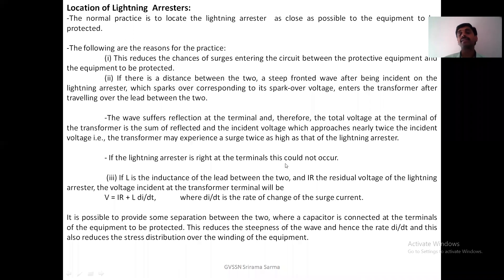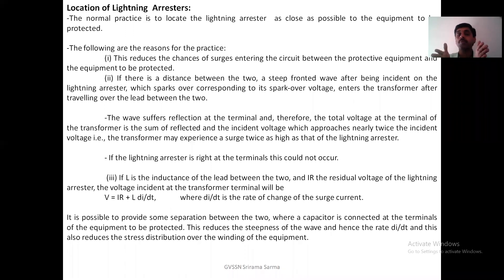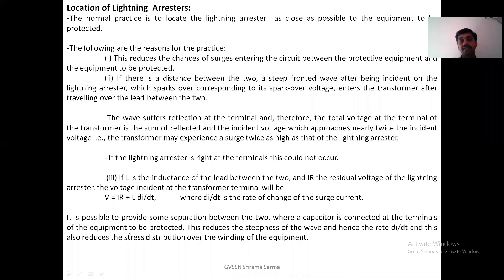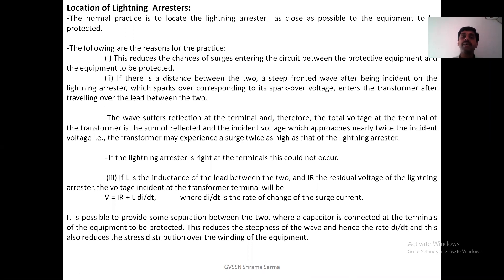Therefore, if the lightning arrester is right at the terminals, this could not occur. Another point: if L is the inductance of the lead between the protective device and the lightning arrester, and if IR is the residual voltage of the lightning arrester, then the voltage incident on the transformer is V = IR + L·(dI/dt), where dI/dt is the rate of change of surge current. If a capacitor is connected at the terminals of the equipment, this reduces the steepness of the wave and hence the rate of dI/dt. That is why we have to locate the lightning arrester as near to the equipment as possible.